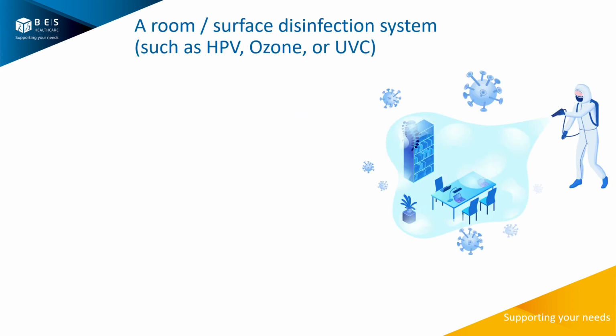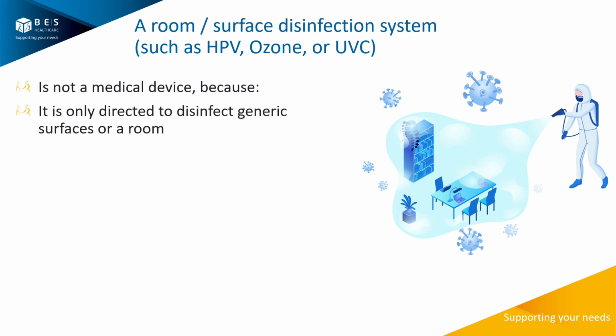So moving on to a different area of disinfection within loan stores, a number of places use hydrogen peroxide vapour systems, ozone or ultraviolet. These are obviously performing disinfection. As far as we're aware, none of these are classified as medical devices because they are only ever directed as generic surface or room disinfection systems. They're not being claimed as medical device disinfectors. That's just not how they're marketed.